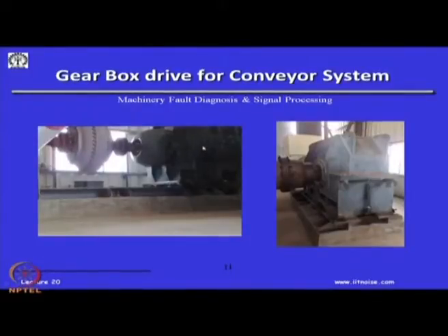These are the bearings, marked 1, 2, etc., for the intermediate shaft, and they are put on a concrete platform onto which there is a steel frame. These steel frames are normally there to ensure that the alignment between the gearbox and the motor is perfect, so that the shaft remains perfectly horizontal. Once we have this steel structure, it is very easy to put in shims so that the alignment can be done, and they can all be manufactured in one piece, and the foundation is put.